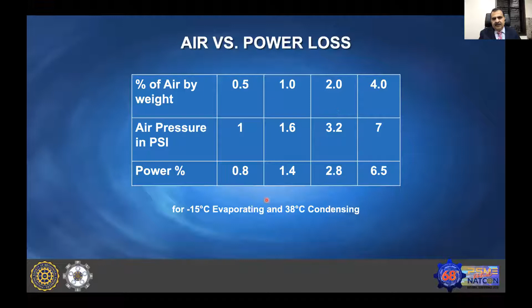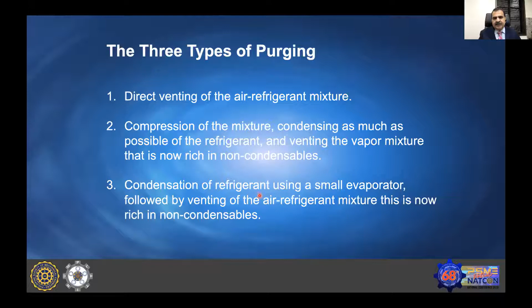Manual purging is doing direct venting from the receiver or condenser, and automatic purging is using purger systems. The purger systems can be made with compression of the mixture and condensing possible refrigerants, or another way is condensation of refrigerant using a small evaporator and using the refrigerant system from the plant. Both systems are available and possible.